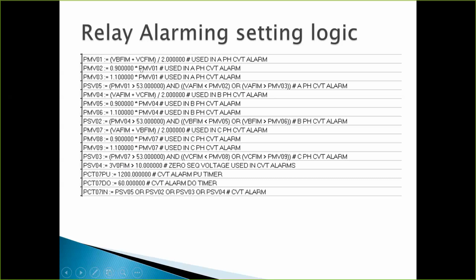Then we take that variable, and we say, is it 10% above or below, okay, and we multiply it by 0.9 or 1.1. We assign that as another variable. So what we've done, we took the average of B phase and C phase, okay. We've multiplied it by 10% above and below right here. We compare that average to a setting of 53 volts. Now, this is important because an alarm setting is different than a loss of potential, okay? A loss of potential, if you lose the secondary voltage, you need to take different action than if you alarm. If you lose it, sometimes we like to accelerate our zone 2 setting. Sometimes we like to block our carrier. So 53 volts is the point we say, okay, if you're at 53 volts, you have a loss of potential.